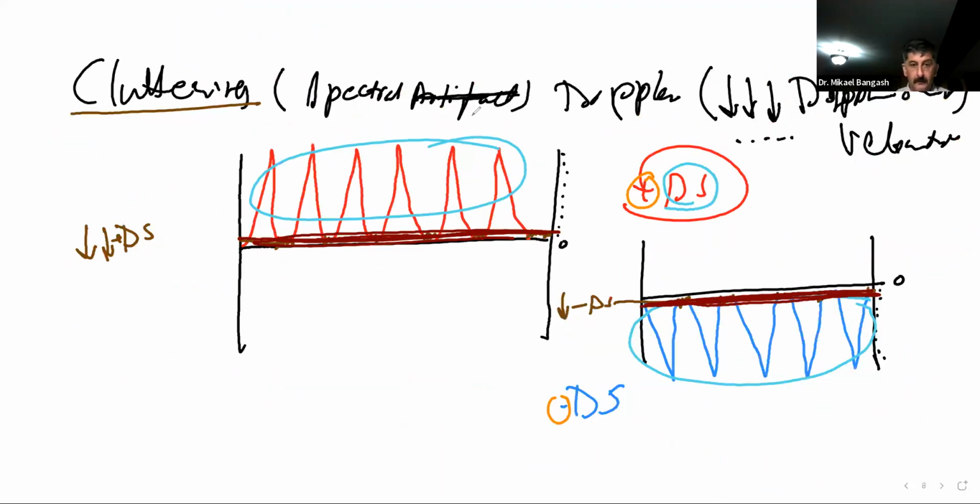Likewise, on your spectral Doppler, you had the cluttering, but as you keep on increasing your wall filter, it doesn't mean that you can do that unlimited. There's going to be a point where you say, this is the limit of the wall filter. Clear? What it will do is only filter the low Doppler shift frequencies, whether on the positive side or the negative side.